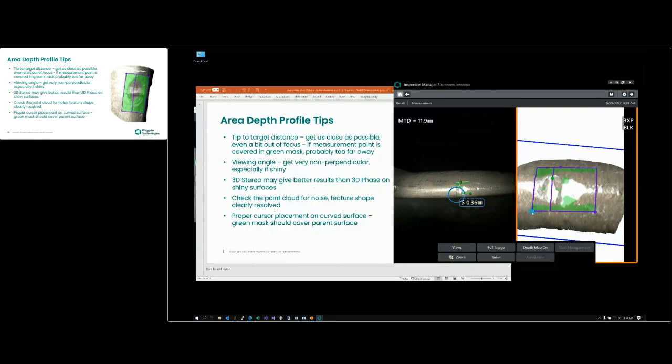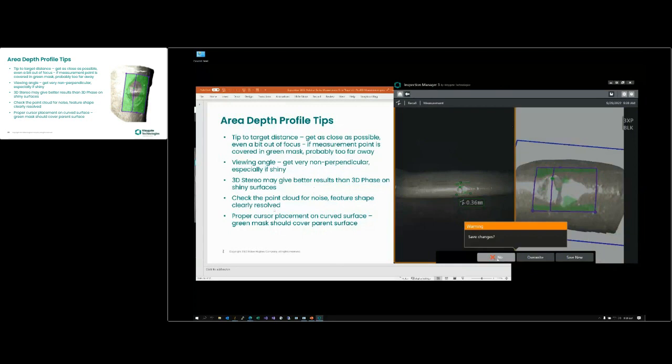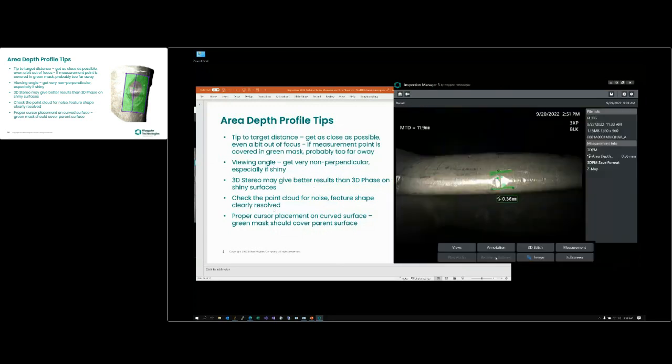And if we look at where the curvature is, it's in the lines running between the reference profiles and not in the reference profiles themselves. So just about everything that could be wrong with this measurement is wrong in this case. So an example of a lot of things you don't want to do.